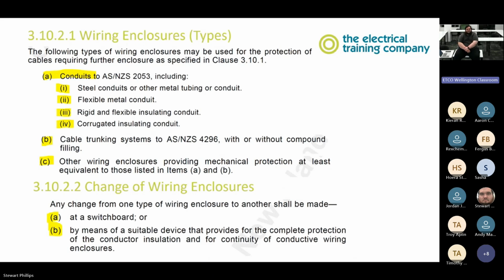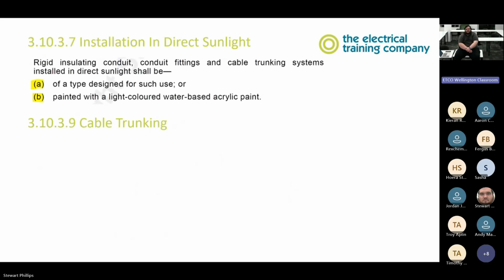Cool. Change of wiring enclosures. Any change from one type of wiring enclosure to another shall be made at a switchboard or by means of a suitable device that provides for the complete protection of the conductor insulation and for continuity of conductive wiring enclosures. So if we're using a steel conduit and we go to plastic, we must make sure that we have continuity of conductive wiring enclosures. So we need to make sure that we run an earth inside of our plastic, which then bonds to our steel conduit. Cool, in direct sunlight, basically making sure that it's a type designed for such use or it is painted with a light colored water-based acrylic paint. So if it is not UV conduit, we can paint it with a light colored water-based acrylic paint.